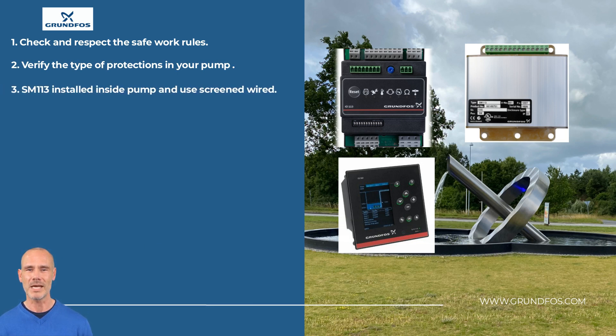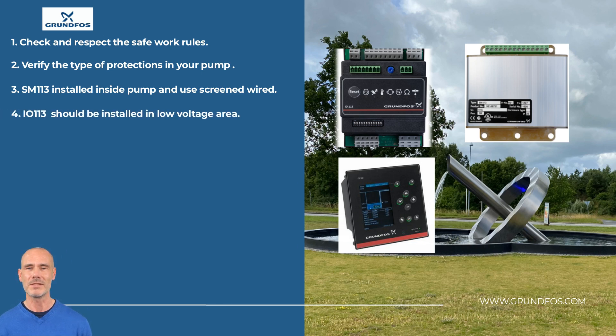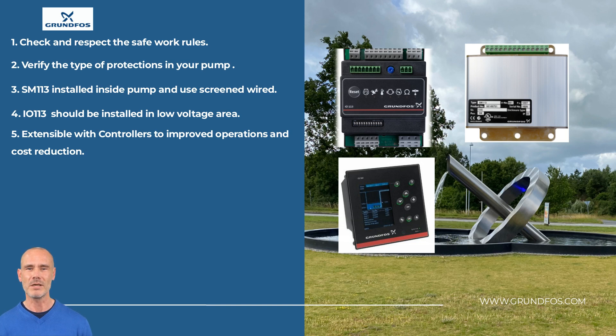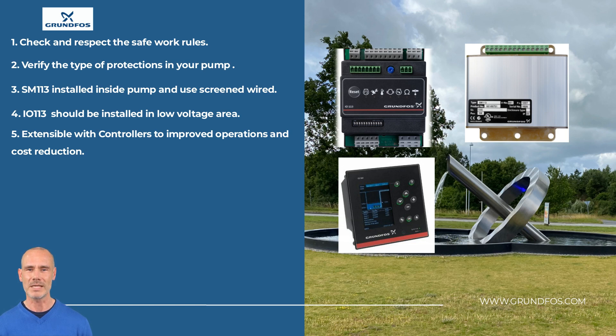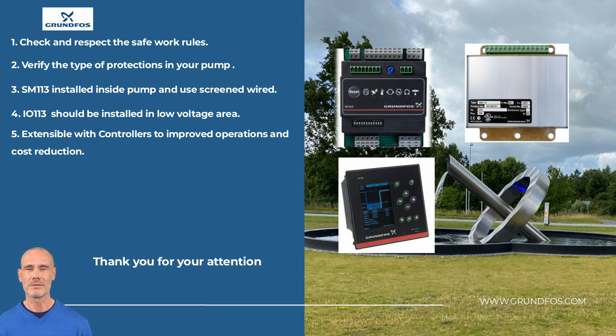The SM-113 installation should be inside the pump. Use screened cable to reduce the noise from other electronic devices. IO-113 should be installed in a low voltage area. To improve the operations and cost reduction, IO-113 installations can be expanded with the Grundfos dedicated control. The purpose of this video is to show a basic generalist example. Always read the manual beforehand and contact your manager if you have questions. Thank you for your attention.